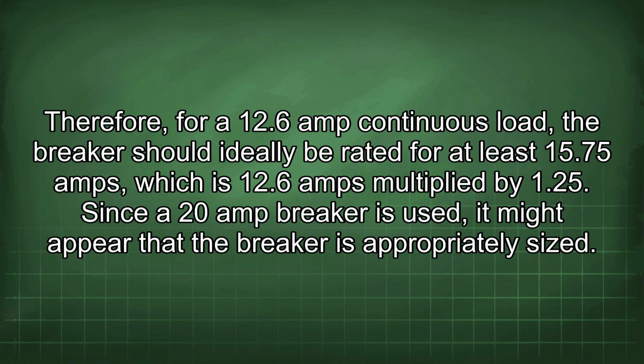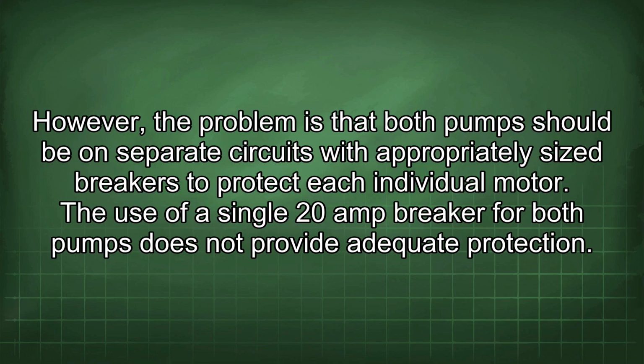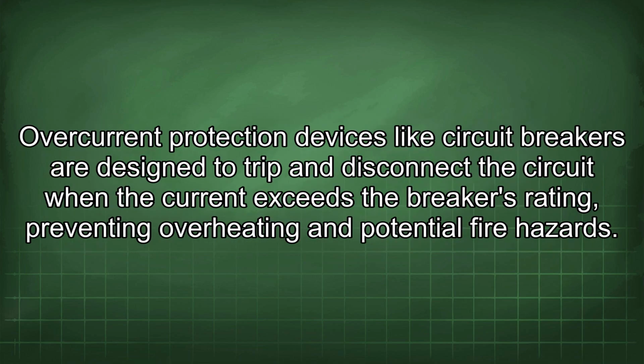Since a 20 amp breaker is used, it might appear that the breaker is appropriately sized. However, the problem is that both pumps should be on separate circuits with appropriately sized breakers to protect each individual motor. The use of a single 20 amp breaker for both pumps does not provide adequate protection. Overcurrent protection devices like circuit breakers are designed to trip and disconnect the circuit when the current exceeds the breaker's rating, preventing overheating and potential fire hazards.